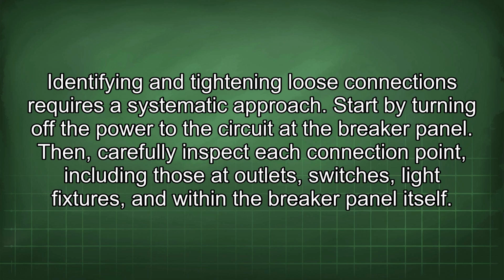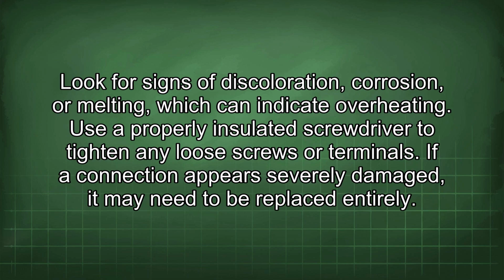Identifying and tightening loose connections requires a systematic approach. Start by turning off the power to the circuit at the breaker panel. Then carefully inspect each connection point, including those at outlets, switches, light fixtures, and within the breaker panel itself. Look for signs of discoloration, corrosion, or melting, which can indicate overheating. Use a properly insulated screwdriver to tighten any loose screws or terminals. If a connection appears severely damaged, it may need to be replaced entirely.